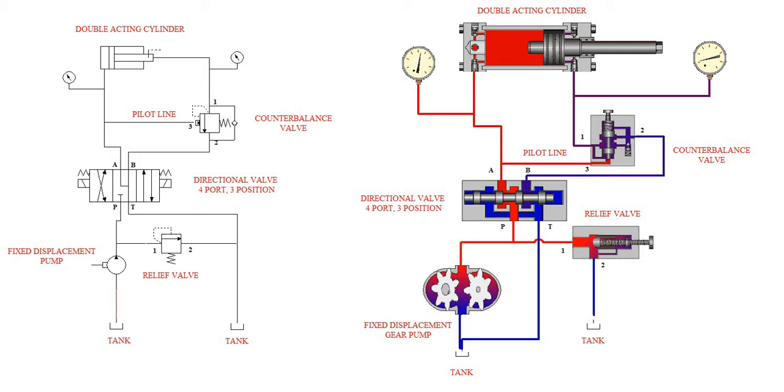Now, another interesting thing between those last two frames is we see our relief valve open back up again. So I'll go back a frame, and you see the relief valve was closed when things were moving along, and then I advance it, it opens up again. So I'll go back again and advance, back and advance, so you can see that relief valve opening up, because now all of a sudden the only way this pump can relieve itself is to elevate its pressure to the setting of this relief valve and go to tank.